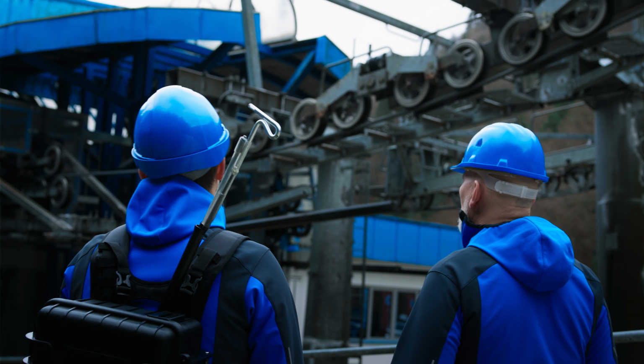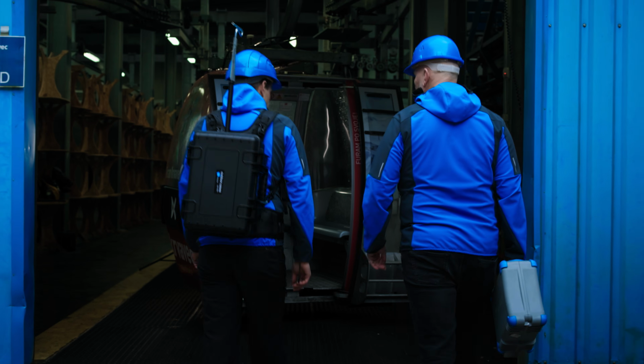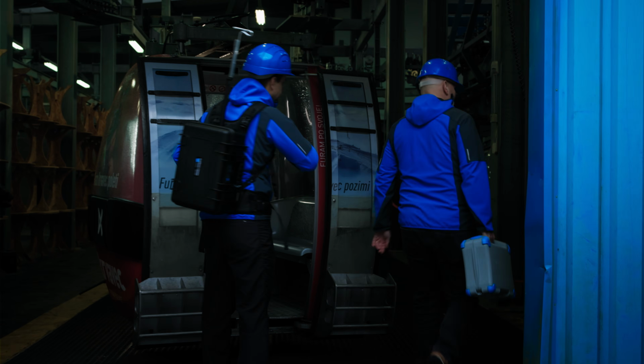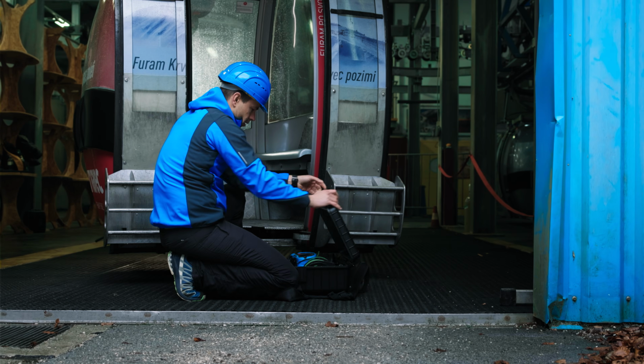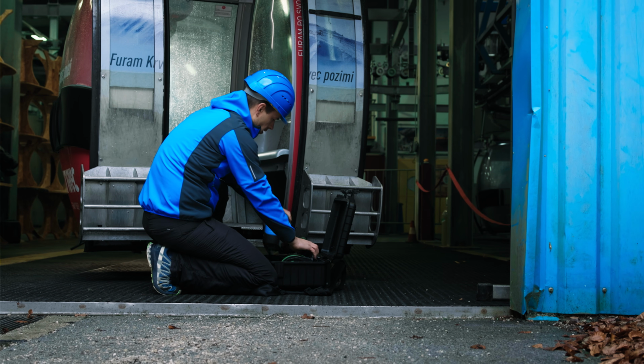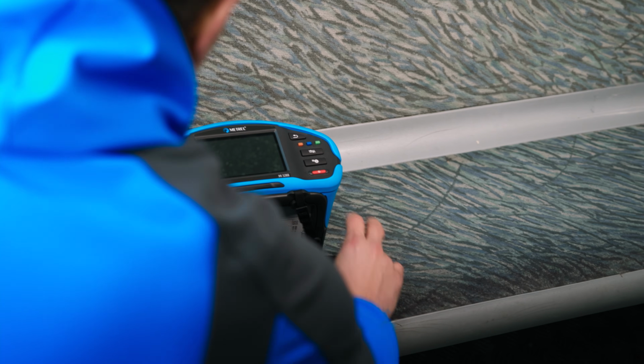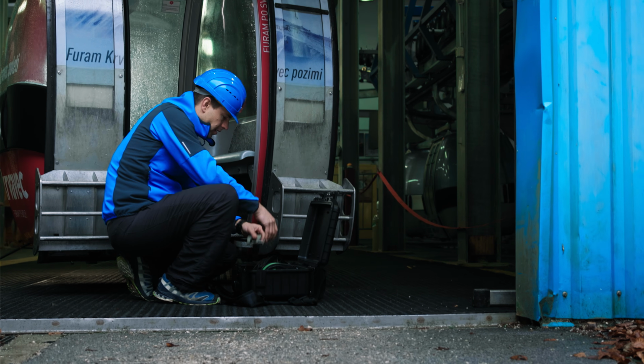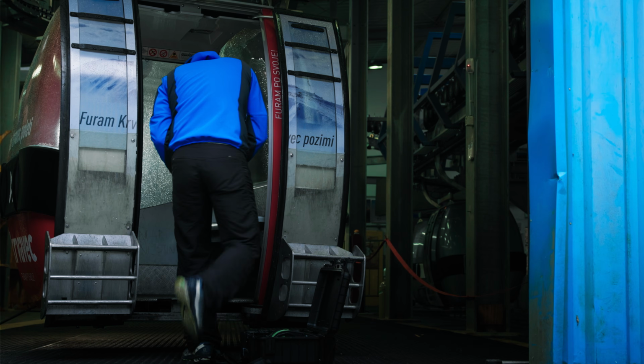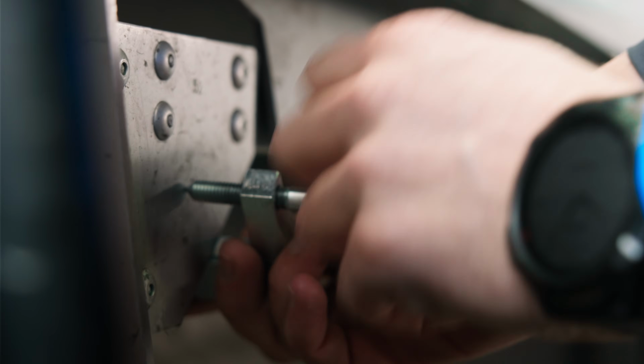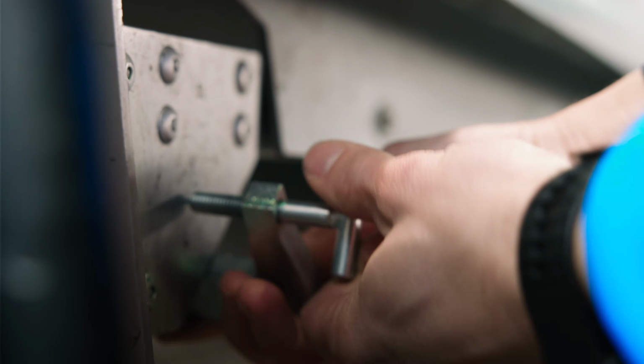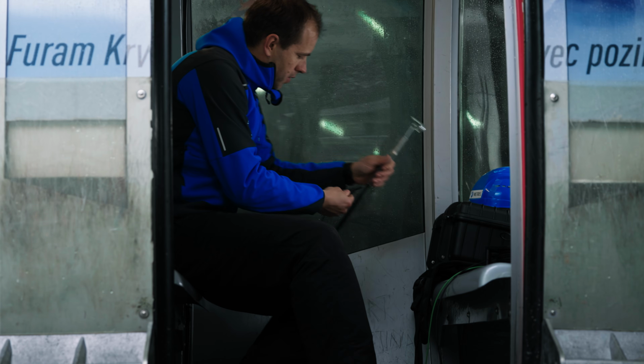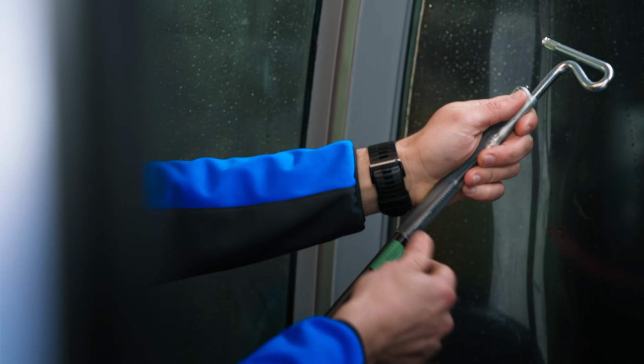Winter is the perfect time to begin, because many tests can be performed while systems are operating. When the carrying cable is grounded during operation, testing becomes simpler. In our case, the cable was not grounded, which required additional steps. Yet the process was still faster and easier than traditional methods. Preparation remains straightforward.